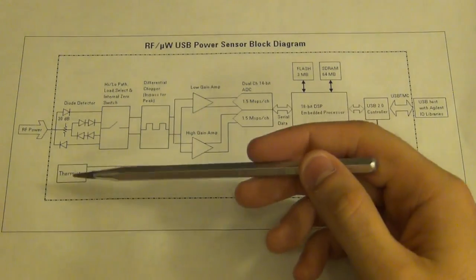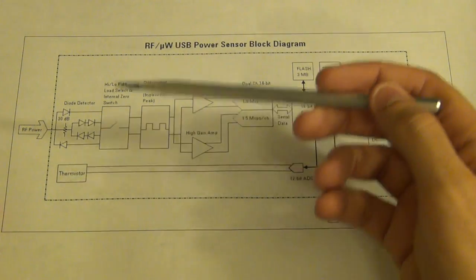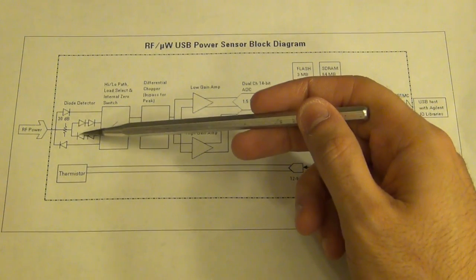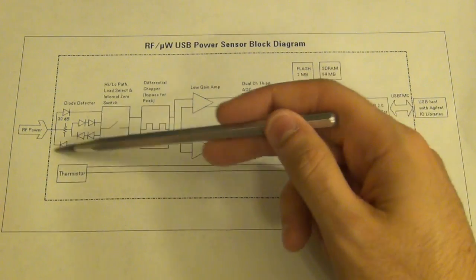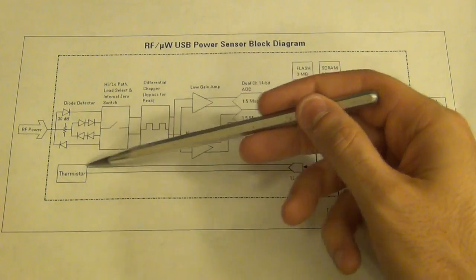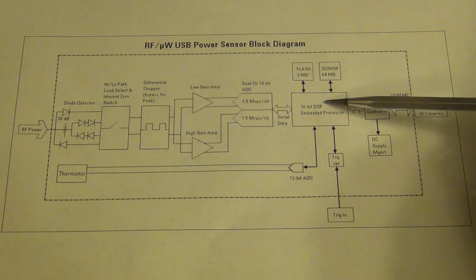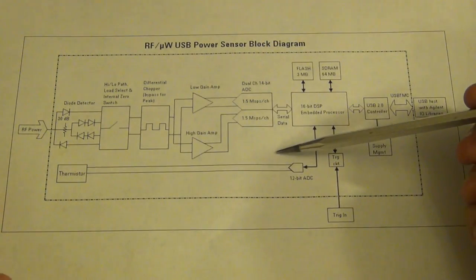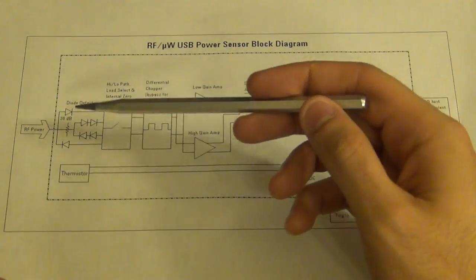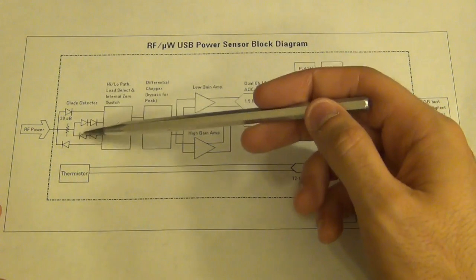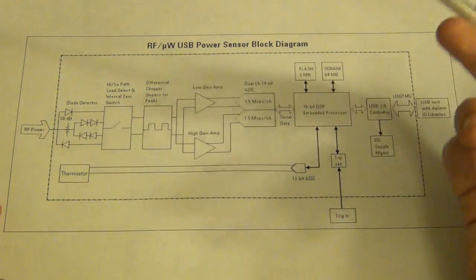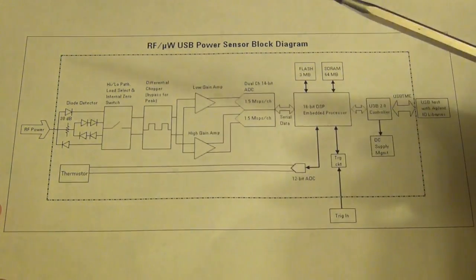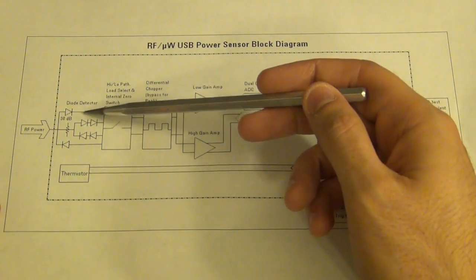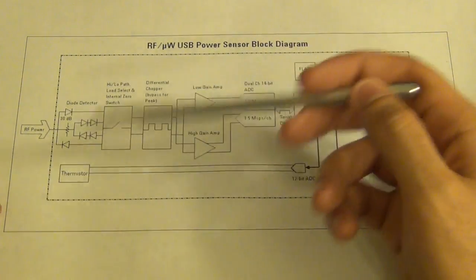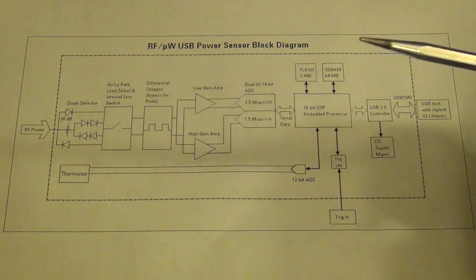At the same time, there's a thermistor sitting right next to these diodes to continuously monitor their temperature, sending that data through another ADC back to the DSP to continuously compensate for temperature so ambient conditions don't affect your measurement. Remember, these diodes have the thermal voltage, 25 millivolts, as part of the exponential equation, and any temperature change affects the junction voltage, which drifts the power reading you're trying to measure.